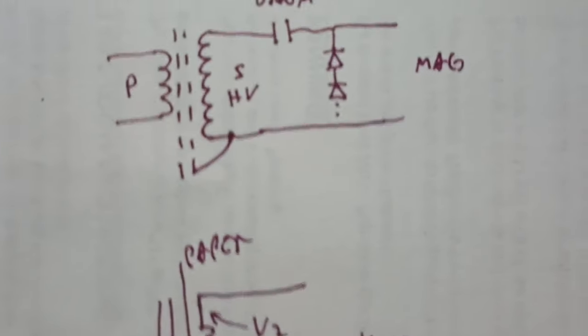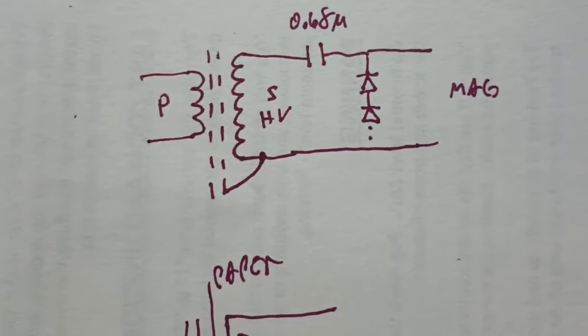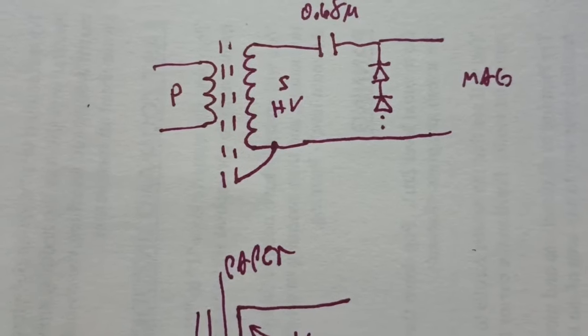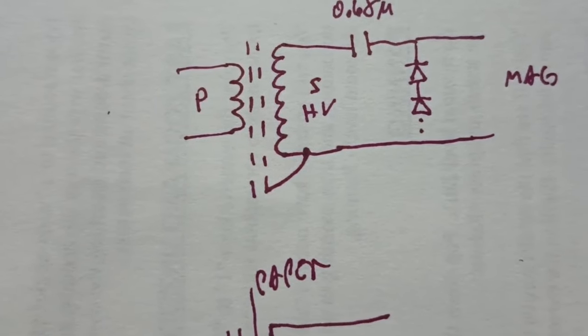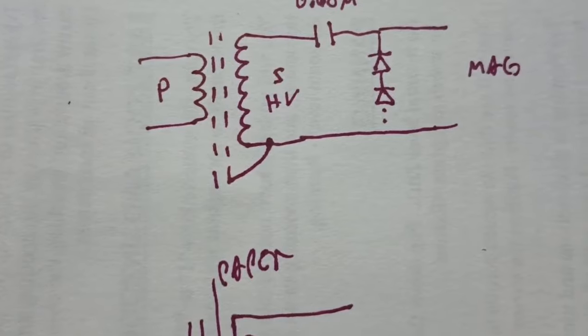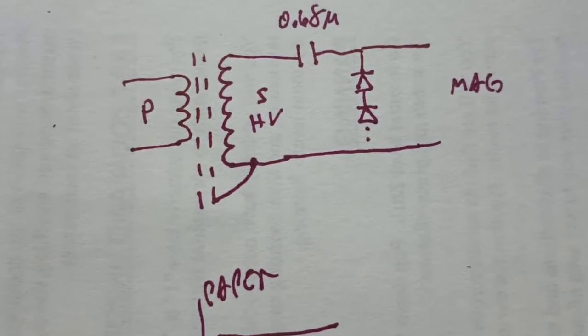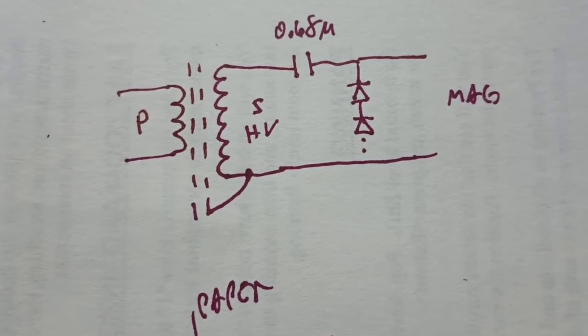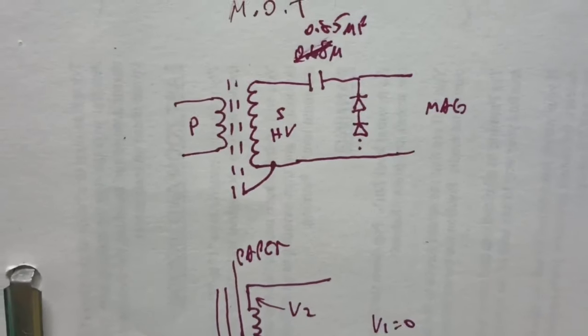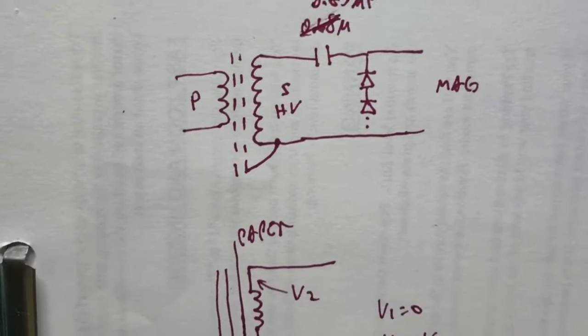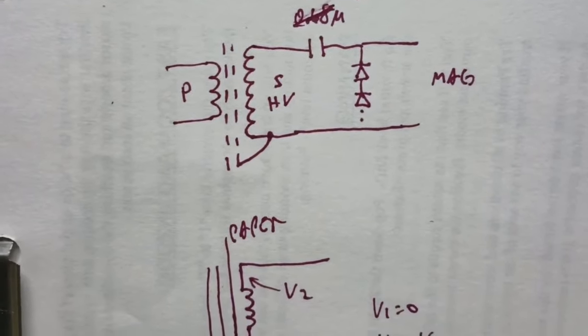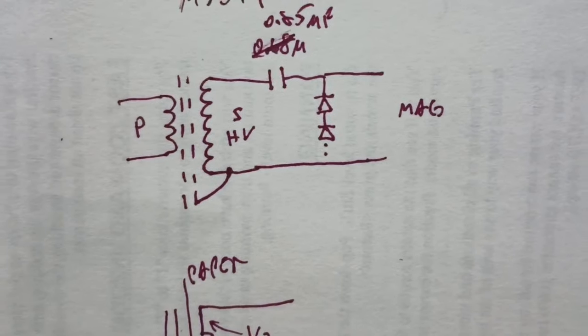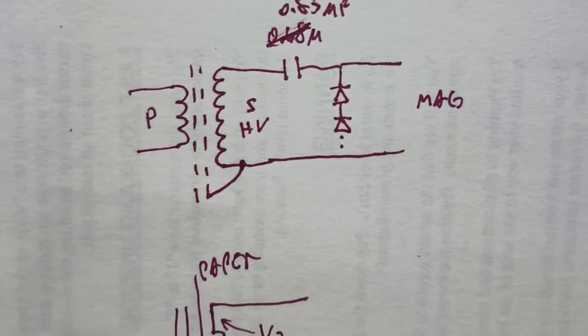So here's the schematic of the original power supply. The high voltage transformer on the left primary, on the right secondary. The bottom side of the winding is riveted to the core in the middle. There's the 0.85 microfarad. It's a very small capacitor. The diode comes off the capacitor and goes to ground. And the first inclination is, oh, that's shorted. Well, if it was short, it would blow a fuse.